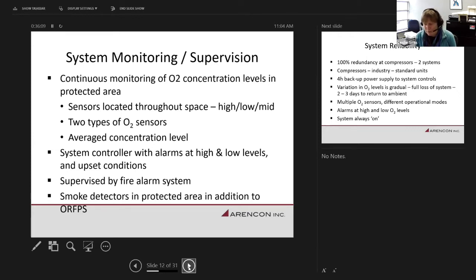A lot of these buildings, warehouses, have automated storage retrieval systems. So they're going to have a form of building automation system, basically a control room watching the conveyors, the in and out, and you can tie in your oxygen reduction fire prevention system. So all the building operators are aware of any conditions. They don't have to go into the plant area to get an alarm from the panel. And then we have smoke detectors in the protected area. So that's in addition and independent of the oxygen reduction fire prevention system. That's just the smoke detectors, and that would feed right into the building fire alarm system or into a fire alarm panel.